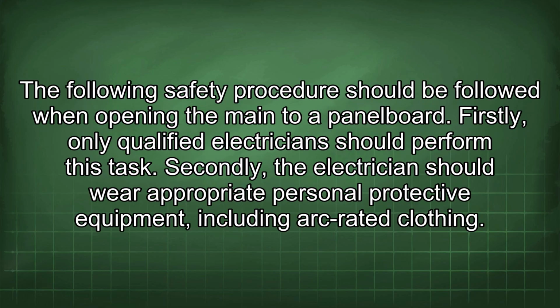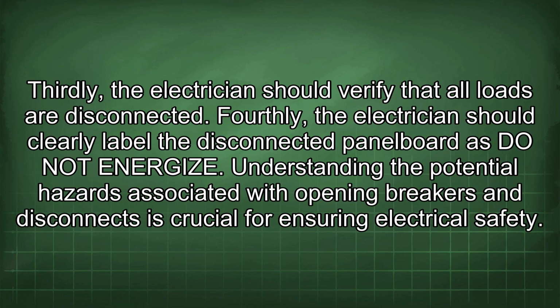The following safety procedure should be followed when opening the main to a panel board. Firstly, only qualified electricians should perform this task. Secondly, the electrician should wear appropriate personal protective equipment, including arc-rated clothing. Thirdly, the electrician should verify that all loads are disconnected. Fourthly, the electrician should clearly label the disconnected panel board as "Do not energize." Understanding the potential hazards associated with opening breakers and disconnects is crucial for ensuring electrical safety.